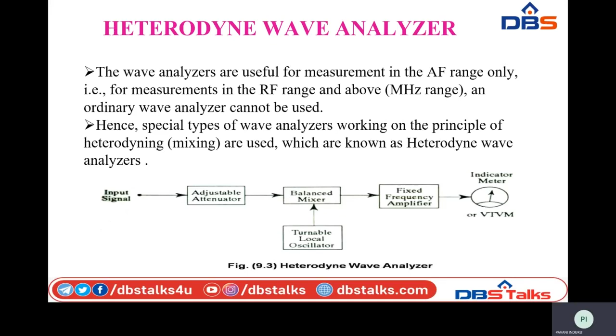So here the input signal is applied to the attenuator, whose frequency is in the range of 0 to 18 megahertz. And then we have an untuned amplifier. So it doesn't tune to particular frequencies, it just amplifies the signal and hands over the maximum power of the signal to the first mixer. So in the first mixer, the input signal with frequency from 0 to 18 megahertz is mixed with a local oscillator whose frequency can be adjusted from 30 to 48 megahertz with the help of a tunable frequency range control.